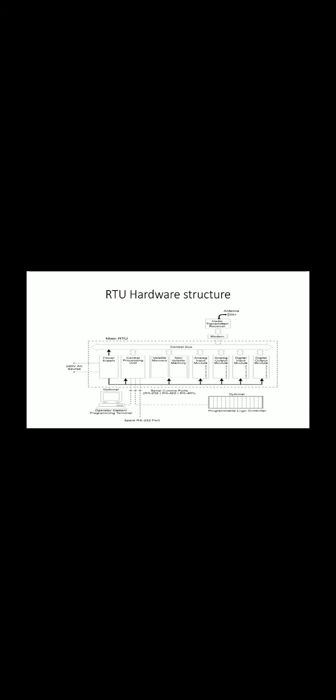Now, see, the RTU hardware structure is being shown in the figure. The RTU rack operating at the electric station is being shown. Next we are going to see telemetry and DAC. The telemetry system is typically used to connect PLCs and RTUs with the control centers, data warehouses, and the enterprises. Examples of wired telemetry media used in the SCADA system include leased telephone lines and the WAN circuit. Examples of the wireless telemetry media can include the satellite, that is VSAT, licensed or unlicensed radio and cellular microwave.